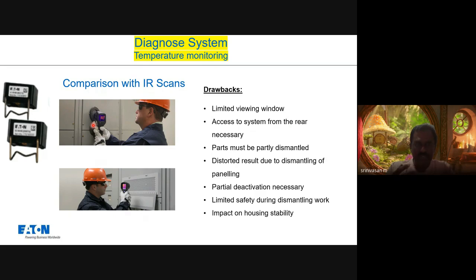Again, if you want to measure the temperature of all the three phases, what do they need to do? They need to remove the door, or remove this cover. The moment you remove the cover or door, we may know most of the substations in this part of the world have air conditioning, so the cool air will go inside. So whatever temperature you are measuring is not the realistic value. Also, there is a safety concern the moment you open the door or the protective shrouds inside. It also requires some skill to take the exact measurement, at which angle we are focusing towards the hotspot. So these are all drawbacks of this conventional thermographic study.